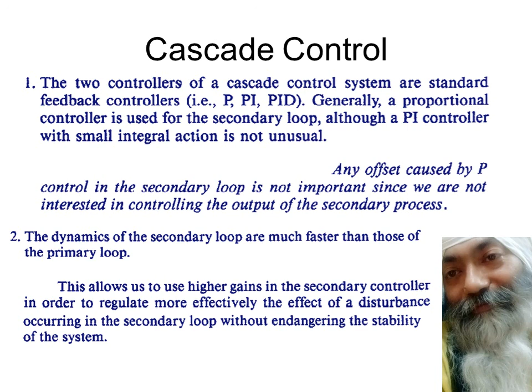Second thing, as I've been telling you, is that the dynamics of the secondary loop are faster than those of the primary loop. That's why the slave has to be faster than the master. This allows us to use higher gains in the secondary controller to regulate more effectively the effect of disturbance occurring in the secondary loop without endangering the stability of the system. Because the dynamics are faster, we can have higher gains without disturbing the stability. And once again, for the last time, we first tune the secondary or the slave controller and then the master. This is the last comment on cascade control.